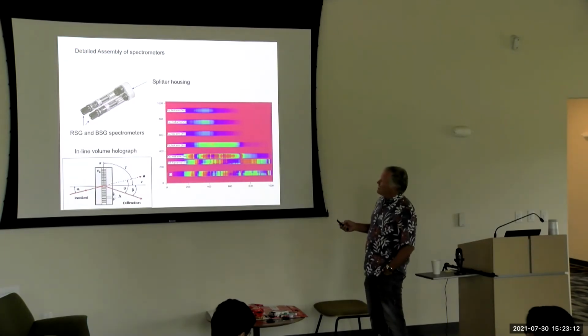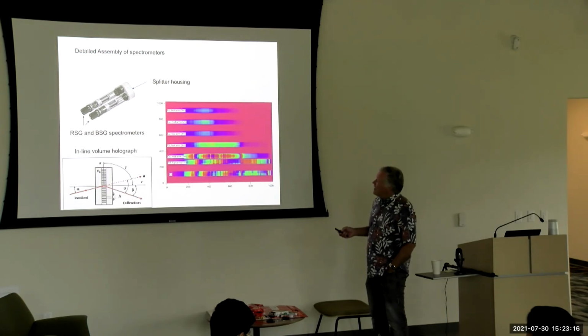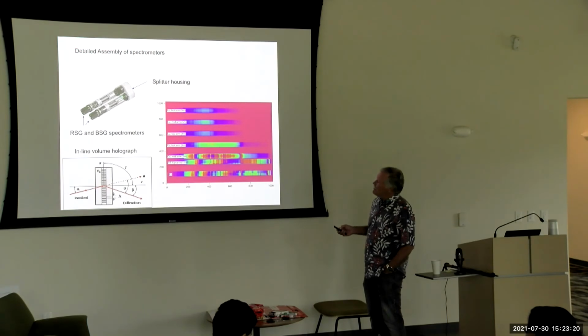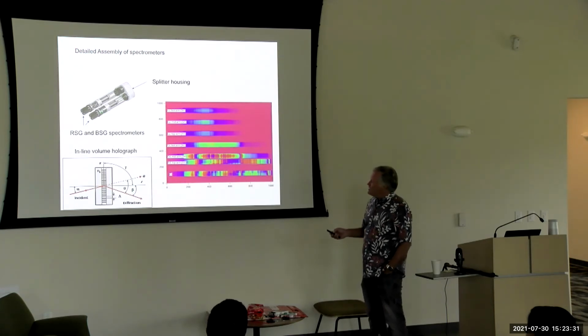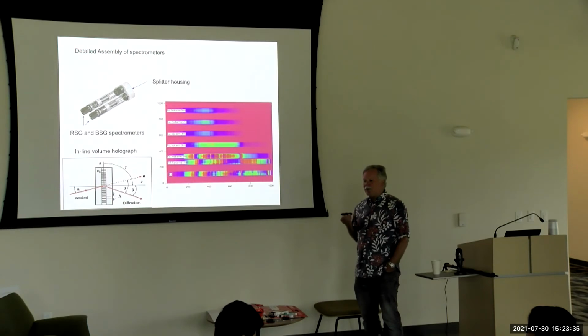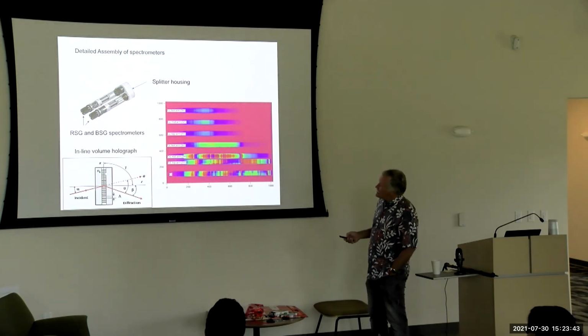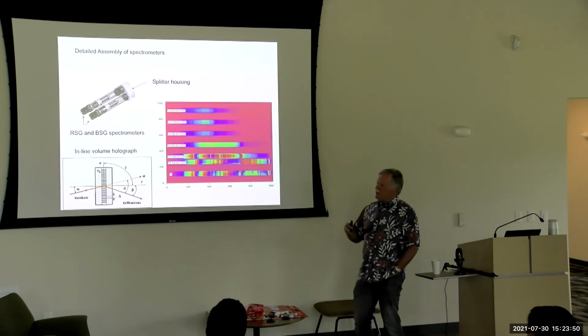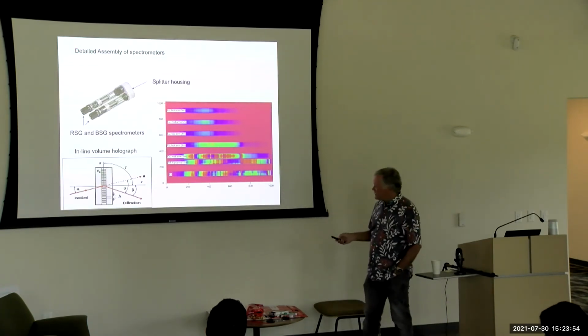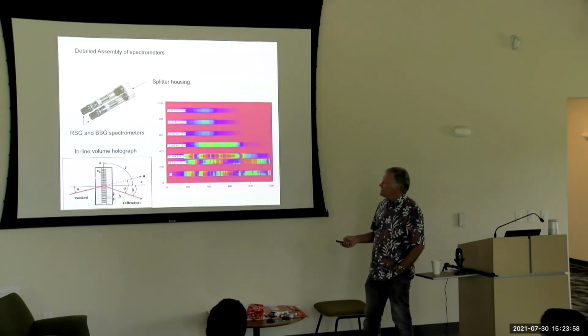So I'm going to go through sort of assembly, the spectrometers we have with our new system. Basically, there's once again a red and a blue spectrometer, and then a splitter housing that splits the light that comes into this piece from the different fibers of the arms and goes to either red or blue spectrometers. The spectrometers, instead of the current system, use a reflective holographic grating to do the diffraction and change the wavelengths. These things use these inline volume holographs. So basically, there's a gelatin here that they imprint an index of refraction gradient in, and that gelatin's between two pieces of glass. So going through this grating effectively diffracts the light and spreads it out by wavelength.